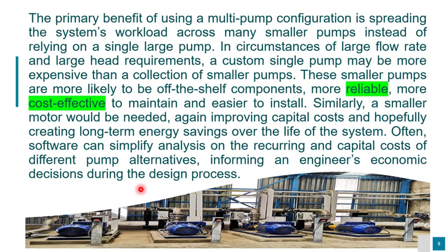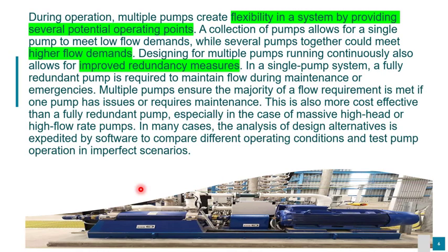Often, software can simply analyze the recurring and capital costs of different pump alternatives, informing an engineer's economic decisions during the design process. During operation, multiple pumps create flexibility in a system by providing several potential operating points. A collection of pumps allows for a single pump to meet low flow demands, while several pumps together could meet higher flow demands. Designing for multiple pumps running continuously also allows for improved redundancy measures.